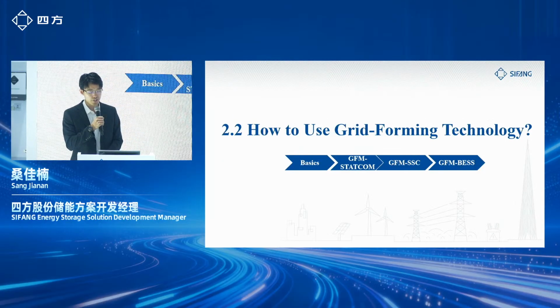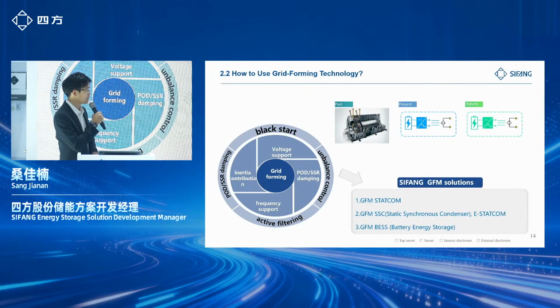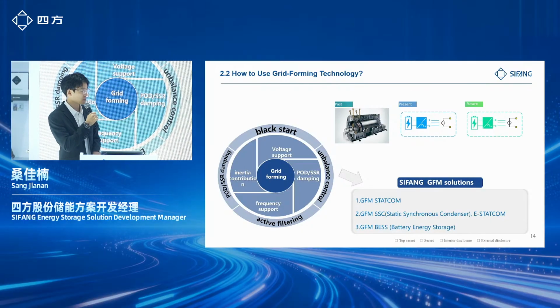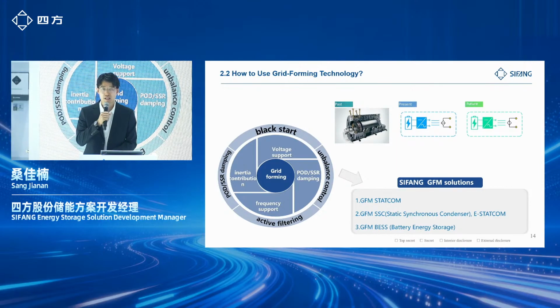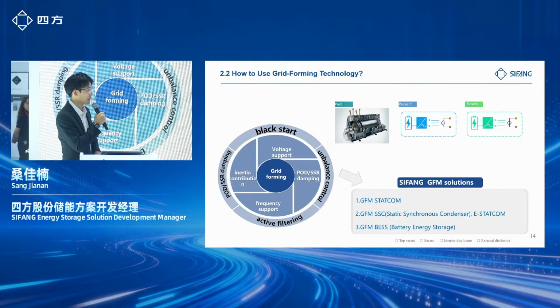So how to use grid-forming technology? With that background, the Sifang grid-forming solutions give you three options. We have three products to be used in different scenarios. The first one is Grid-Forming STATCOM. That is the traditional solution, grid-forming. The second one is Grid-Forming SSC, which means static synchronous condenser for short. It also has another name, E-STATCOM. E means energy STATCOM, because it adopts a supercapacitor on the DC side, which adds energy to it. The last solution is Grid-Forming BESS, battery energy storage.